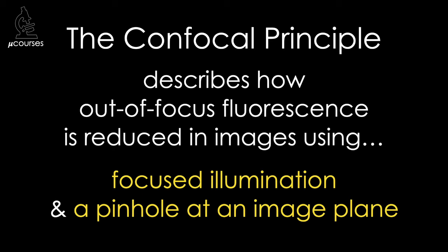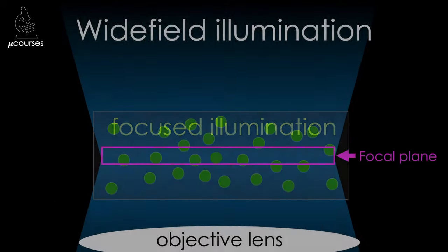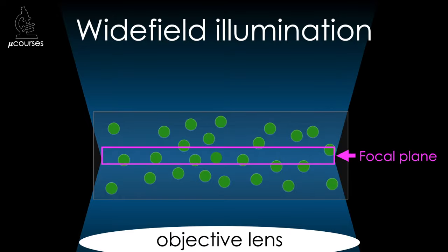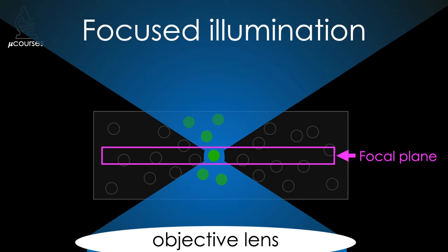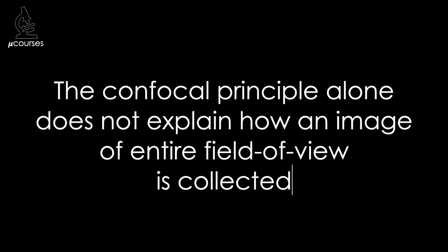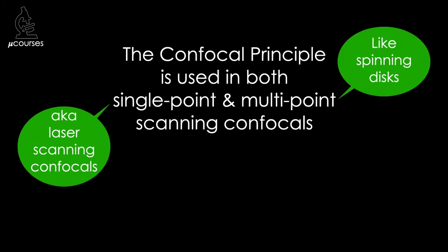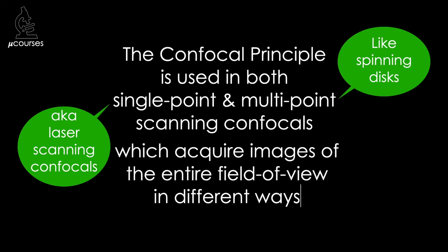Let's work through the details of the confocal principle, beginning with the first feature: focused illumination. Under wide-field illumination, the entire field of view is illuminated. Focused illumination means that the illumination light is focused into a small point in the focal plane of the objective lens. The confocal principle described here does not alone explain how an image of the entire field of view is collected — the confocal principle is used in both single-point and multi-point scanning confocals, which acquire images of the entire field of view in different ways. How these instruments utilize the confocal principle are topics for another microcourse.